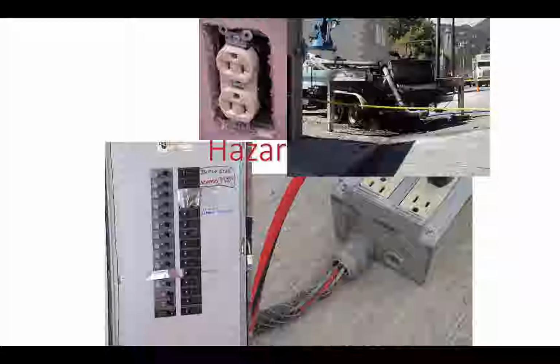Okay, electrical hazards are everywhere. There's no way you're going to work in the construction industry and not come across potential electrical hazards. Okay, if we take a look at this picture, you can identify several electrical hazards and several issues that should be corrected. So, just to really quickly run down here, if you take a look at the breaker panel cover on the left, we have duct tape covering empty holes. We have an outlet cover that's not on and the screws are exposed. We have a crane that is probably touching power lines above it. And we have an outlet that has exposed wiring and the insulation cover is pulled back. All of these are hazards when it comes to electrical.